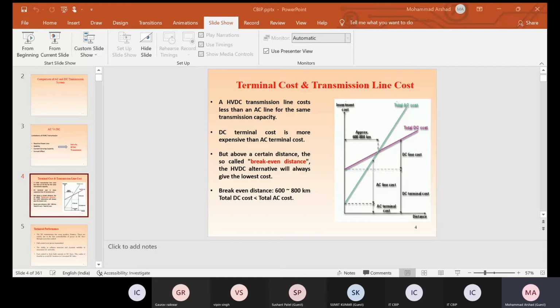AC terminal cost is lower because we don't have those thyristor valves, converter transformers, filters, and all that. So if my break-even distance is 600 to 800 kilometers, then if I want to transmit power greater than 800 kilometers, I will go for the DC system, right?